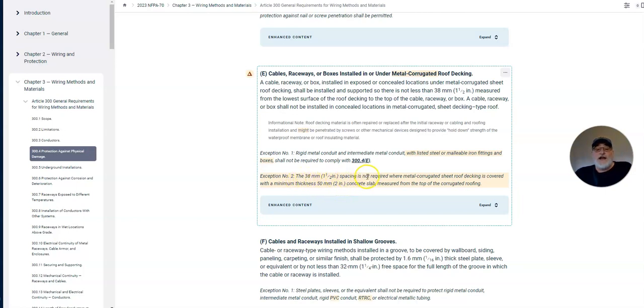Exception 2: the 1.5-inch spacing is not required where metal corrugated sheet roof decking is covered with a minimum thickness of 2 inches of concrete slab, measured from the top of the corrugated roofing. That specific exception is there because they use this same corrugated material when building multi-story buildings. As long as you're not on the roof deck, the very top, once you're below that roof deck, say it's a 5-story building, as long as you're on floors 4, 3, and 2 in their ceilings, respectively, and floor 1 ceiling, you can run that stuff up there with this exception, which saves you time, effort, and hate and discontent, believe it or not.